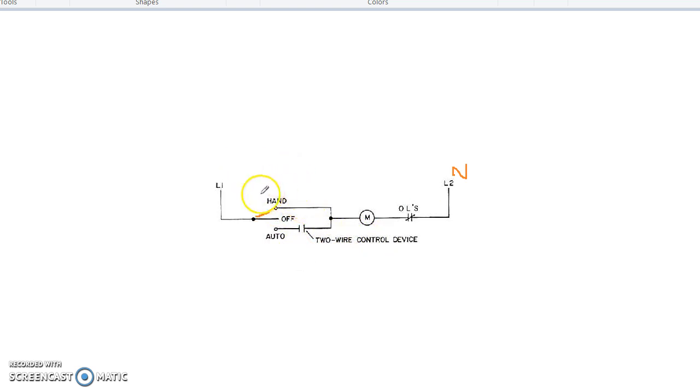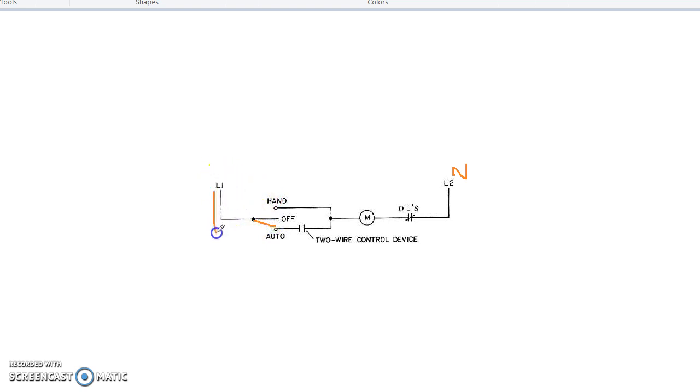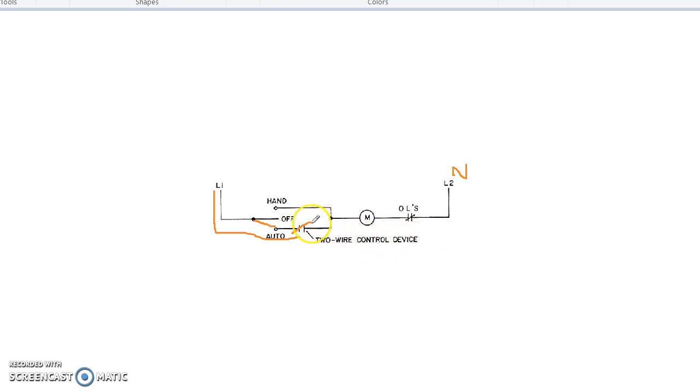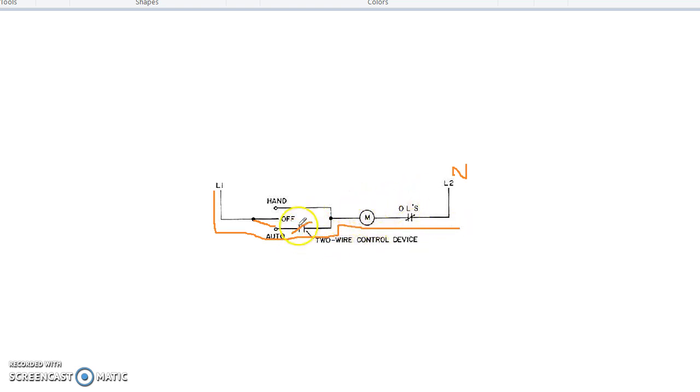Let's start now if it was in auto. If it was in auto, the current will flow like this. And according to the signal, if this is closed, if we receive the signal from SCADA to run the motor, this will close and the current will continue, this will run the motor.